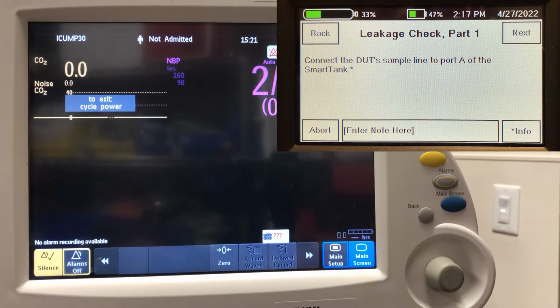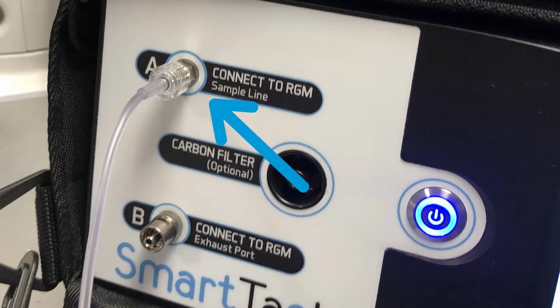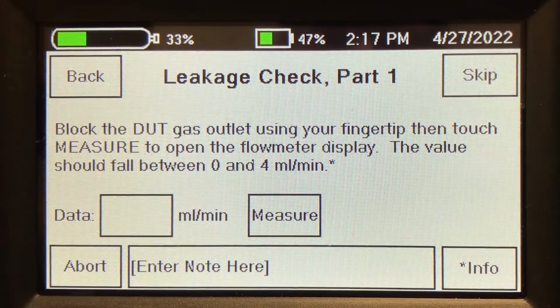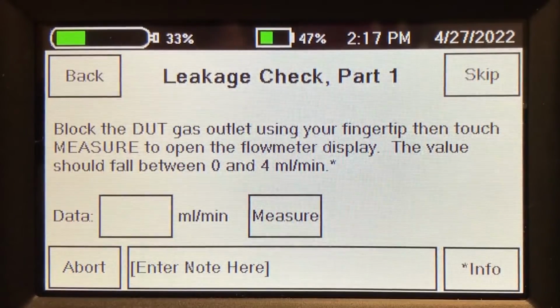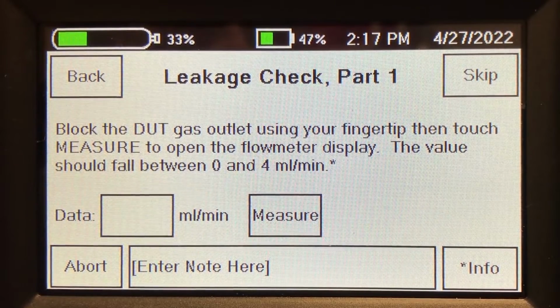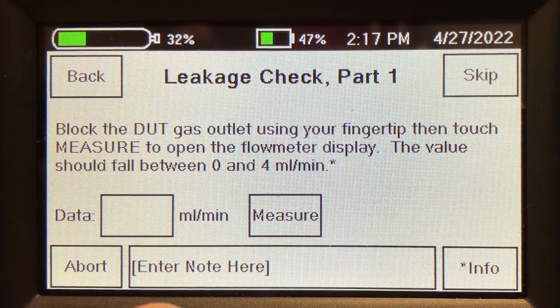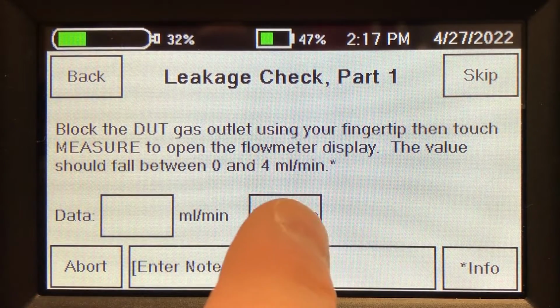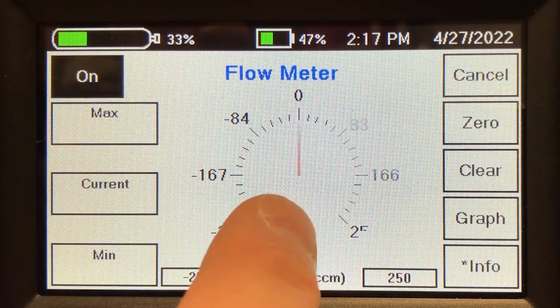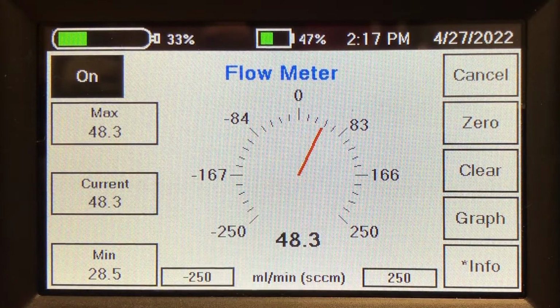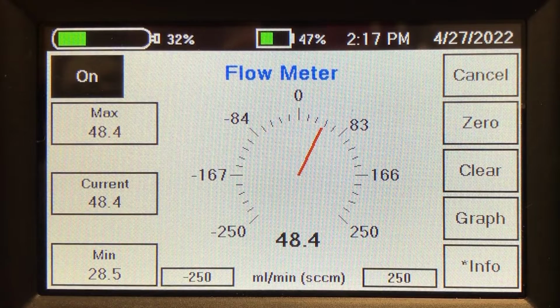So we're going to connect the sample line to port A on the smart tank, and we are going to use our finger to block the exhaust port on the device being tested on the extension module, and you'll hear the pump speed up. We hit measure, and I'll do that again. So here I'm not blocking the exhaust port right now. You can see the flow is 48.4.